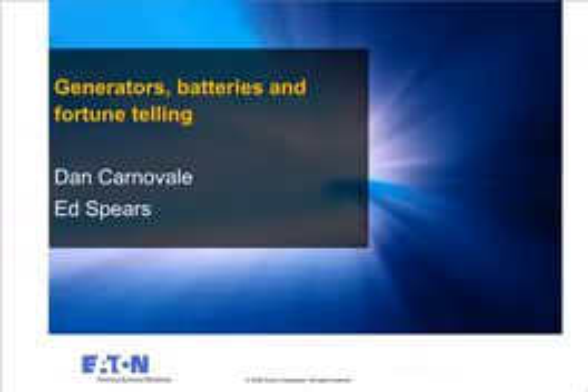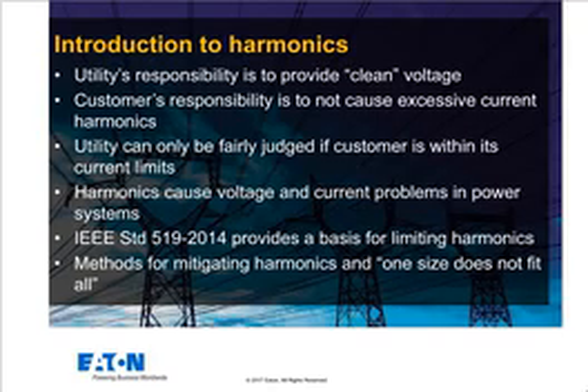So I almost always start off a conversation around harmonics with this statement, which is, harmonics are not a problem unless they're a problem. So what does that really mean? When we discuss harmonics, the problems associated with that can be problems on the utility side that affects other customers, or it could be on the customer side itself, the people that are using the power.